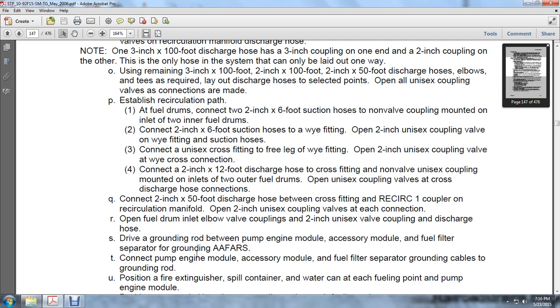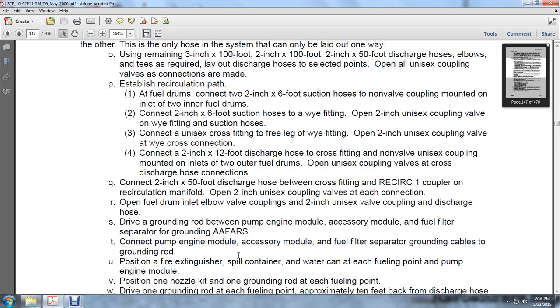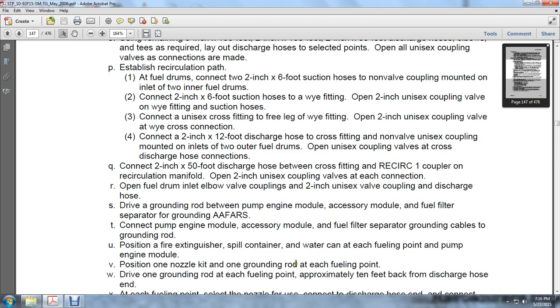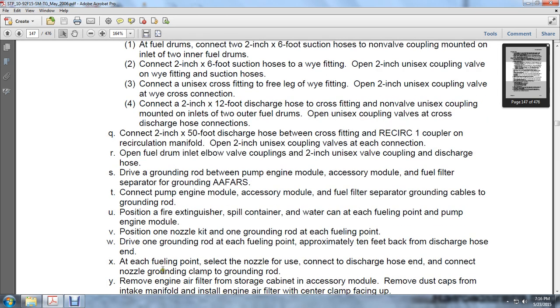Position a fire extinguisher and spill container at each fuel point and at the pump and engine module. Position one nozzle kit and one ground rod at each of the fueling points. Drive the ground rod at each fueling point approximately 10 feet back from the discharge hose end. At each fueling point, select the nozzle for use. Connect the discharge hose at the end, and connect the nozzle ground clamp to the ground rod.